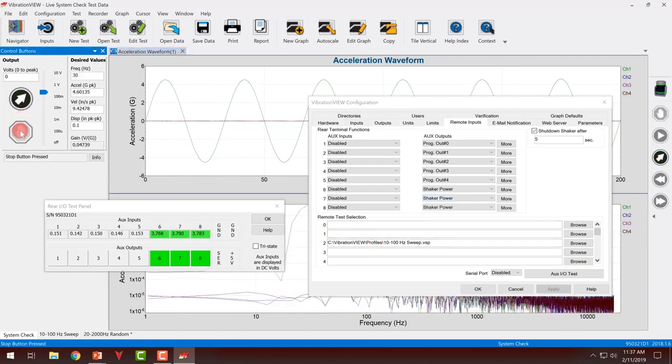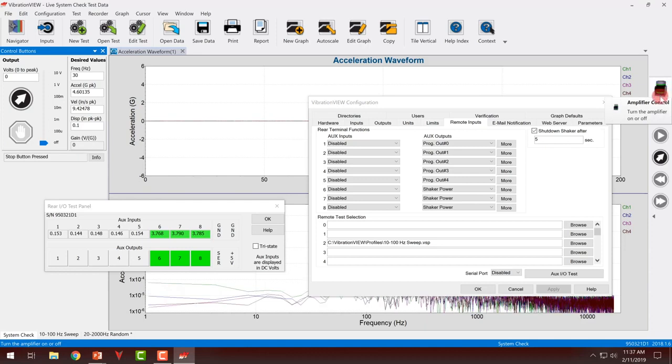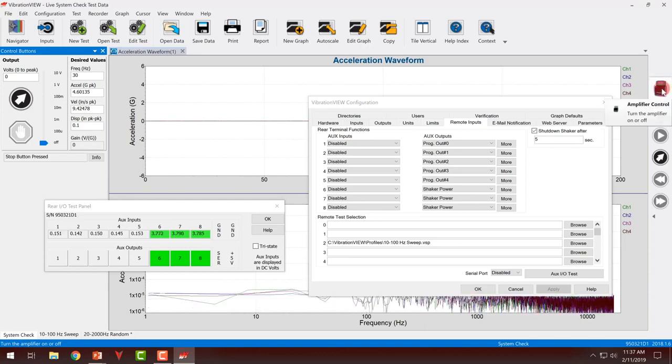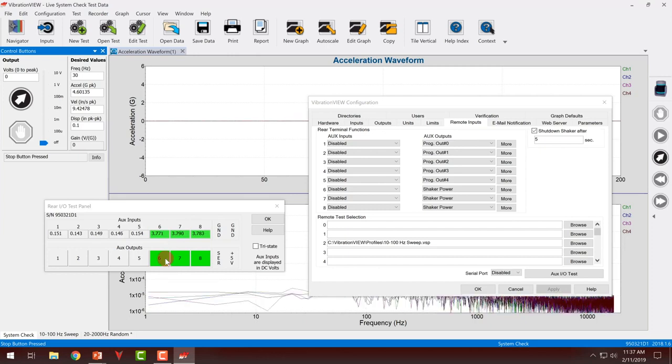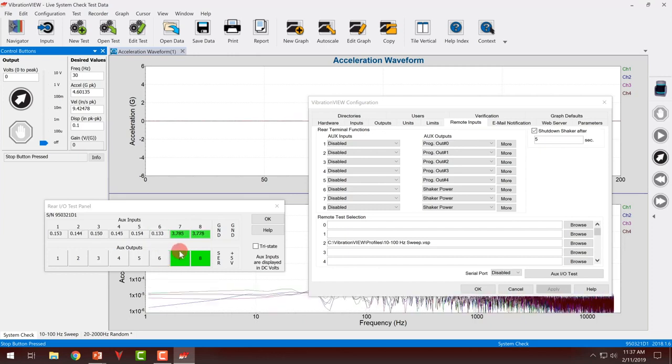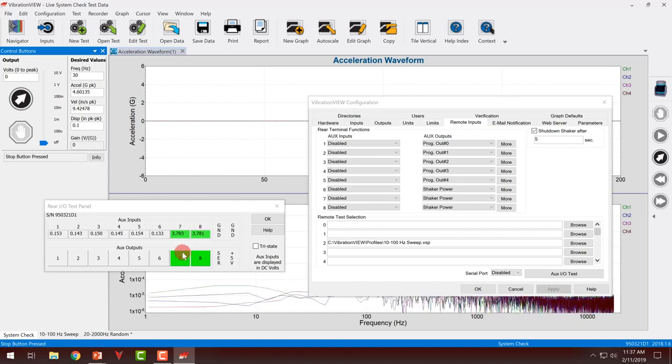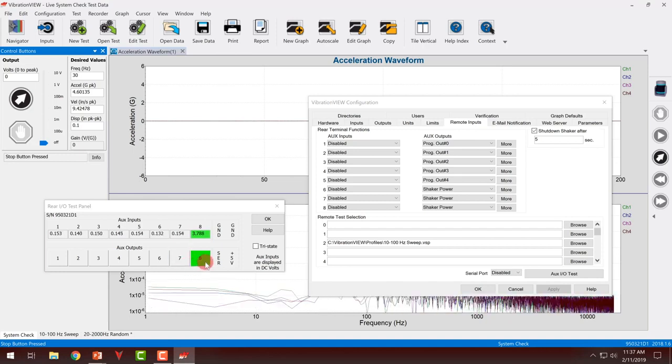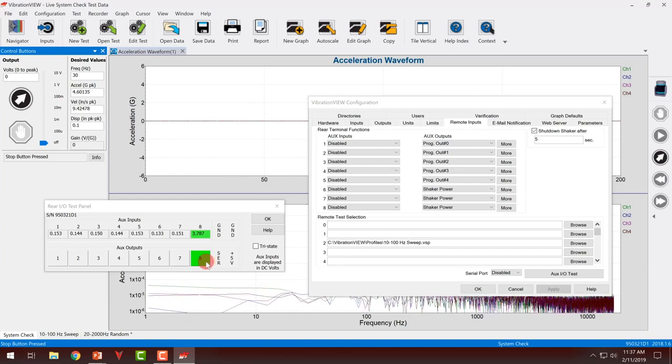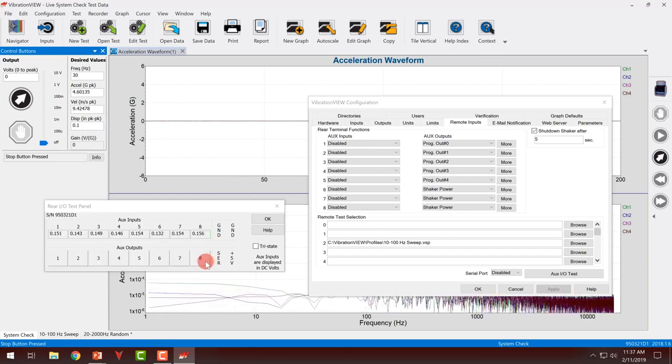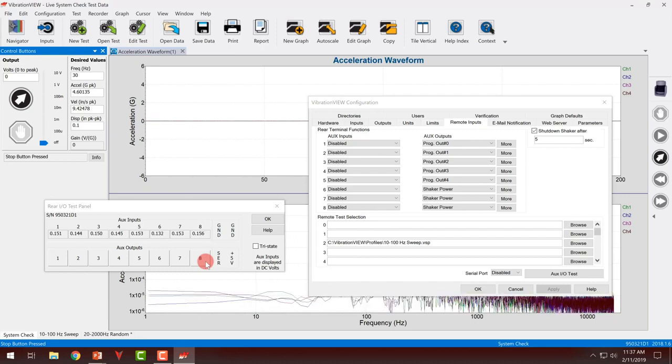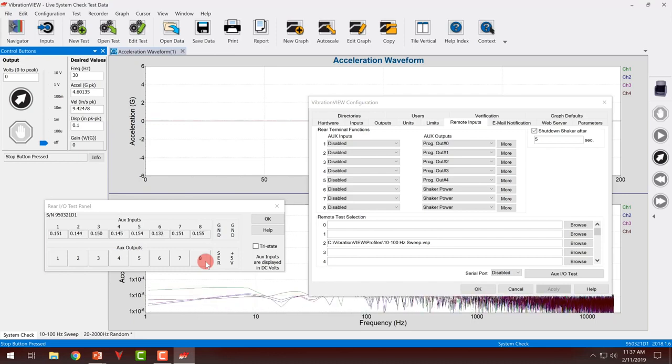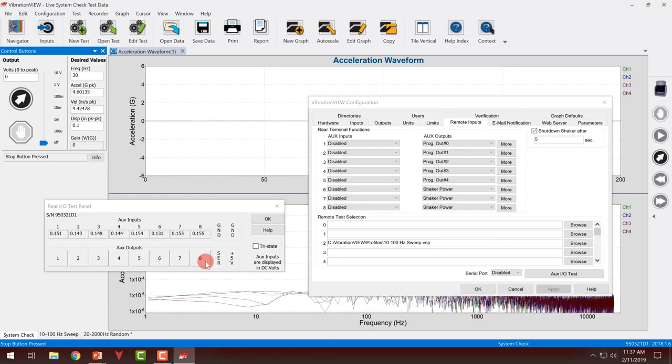So if I hit stop, you can see the sequence execute with each output turning off after the configured delay. That is my shutdown sequence. Obviously, my timing is purely for demonstration, but that gives you the general idea.